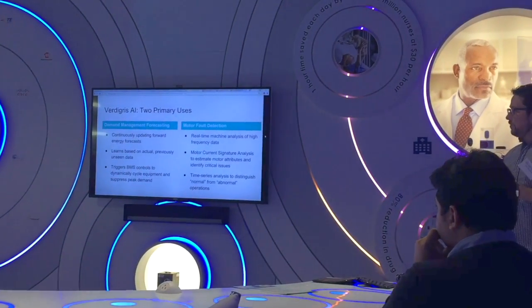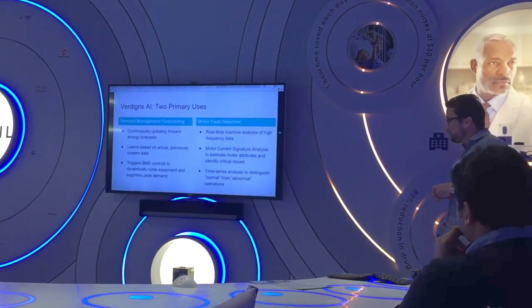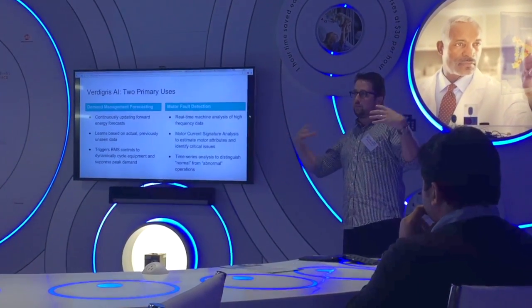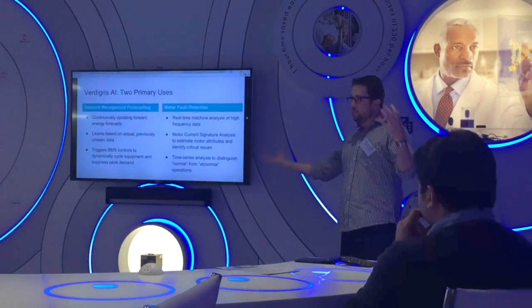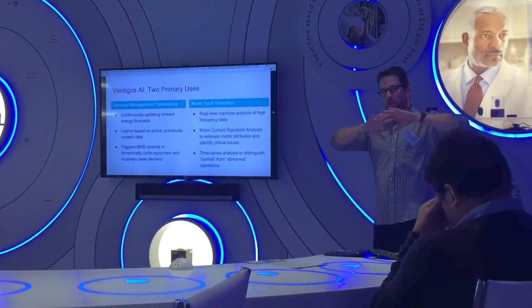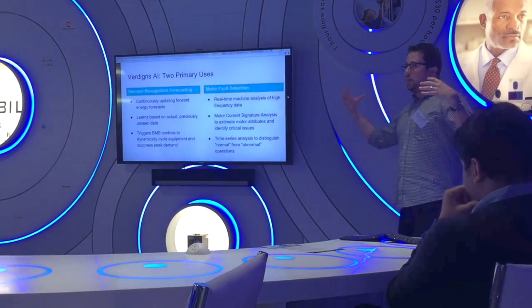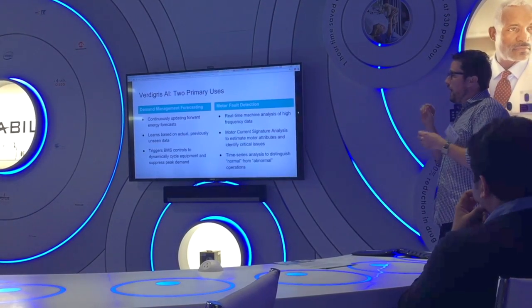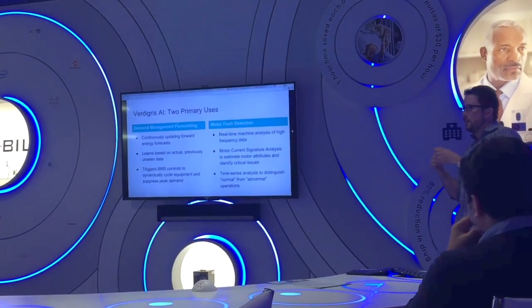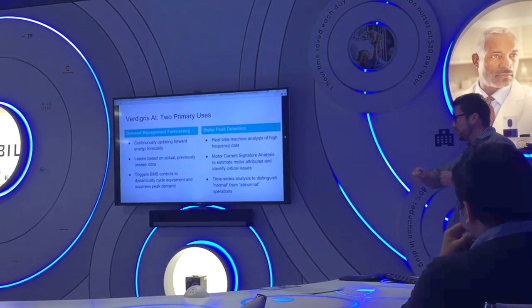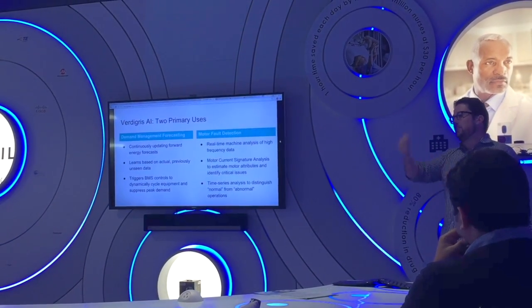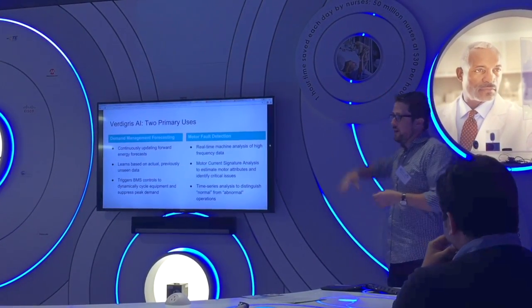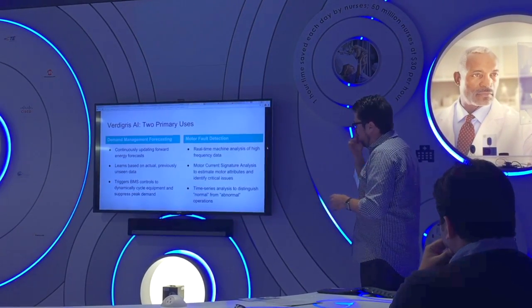And so what we can do with that is using the AI's two primary uses: demand management forecasting and motor fault detection. For demand management, we're using this huge amount of very fast, very rich granular data that we're pulling off of all these different devices in the building to construct a really dynamic forecast of what we think is going to happen. We currently forecast every hour and we can use that to do all sorts of things around demand management in terms of tying into a building management system or building automation system and actually affecting changes to the operational profile of the building before you hit those spikes and before you cross those demand thresholds to actively save money.